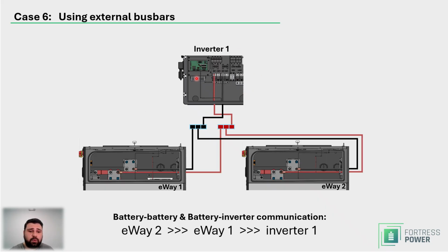So here you have it: inverter 1, eWay 1, and eWay 2. eWay 1 connects to the bus bars, positive and negative. So eWay 1 right here. eWay 2 connects to, again, negative and positive bus bars right here. Note, the cable lengths of all of these must be identical. So on the diagram here, negative for the eWay 1 seems to be shorter, but in reality you would make it the same length as the negative for eWay 2, and again, same length you have for eWay 1 positive and eWay 2 positive. And then from the bus bar you have the connections to the inverter 1.